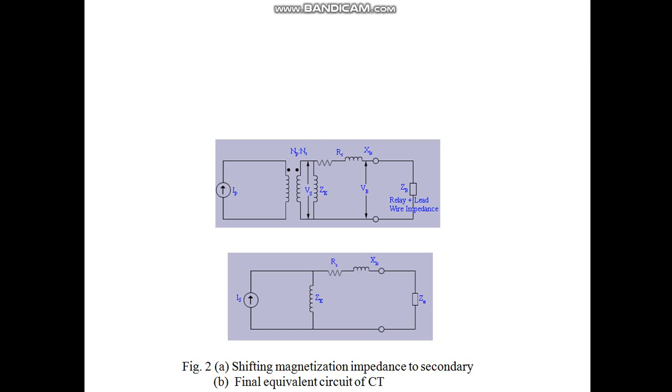If Bm corresponding to the flux is above the knee point, it is more or less obvious that the current transformer will saturate. During saturation, the current transformer secondary winding cannot replicate the primary current accurately, and hence the performance of the current transformer deteriorates. Thus we conclude that in practice, while selecting a current transformer, we should ascertain that it does not saturate on the sinusoidal current that it would be subjected to, with use of numerical relays due to their very small burden.